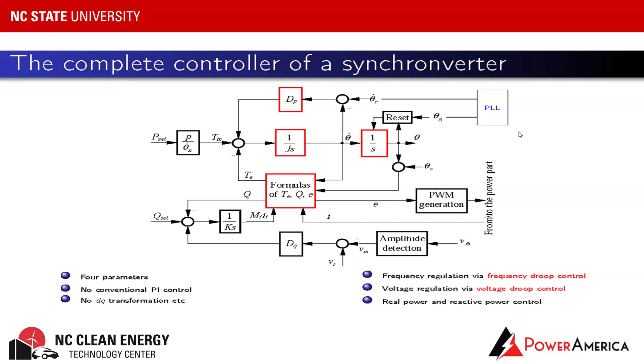Okay. And here we have a phase lock loop, the PLL, for the synchronization purpose. But actually, later we are able to remove this phase lock loop. We don't have to use it. You may have heard that these phase lock loops often cause performance degradations and even instability. So the good news is that we are able to get rid of them. We don't have to use a phase lock loop in a virtual synchronous machine.